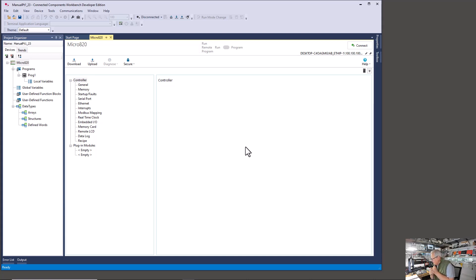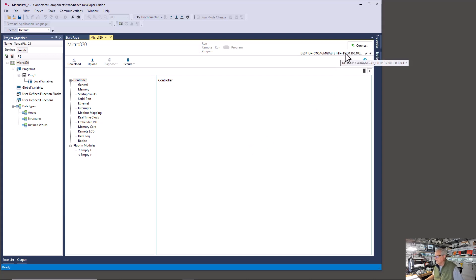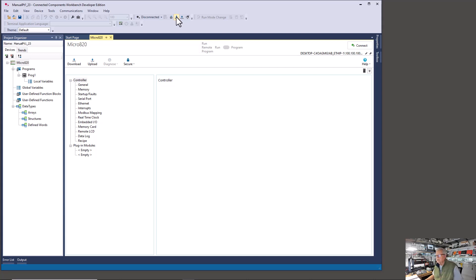So let's explore your first project for the Micro 800. We already did some of this — that is roughly on page 70. But primarily what I'm going to do is download this project and then explore it online. To download, of course, you have to be connected. You see I have a path up there and I am connected. There are two down arrows here: Build and Download. It will always build before you download, but you can build first to see if there are any obvious errors, because if there are errors you have to correct those before you download anyway. So let's just download.